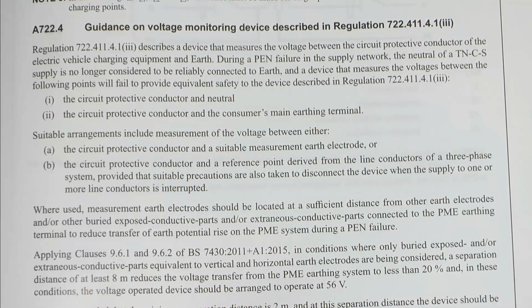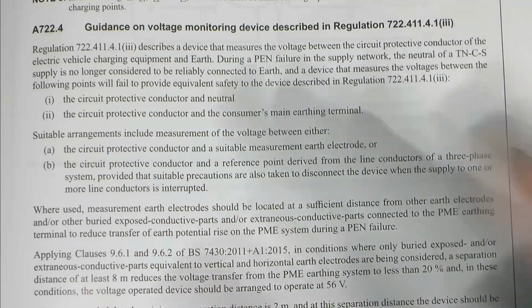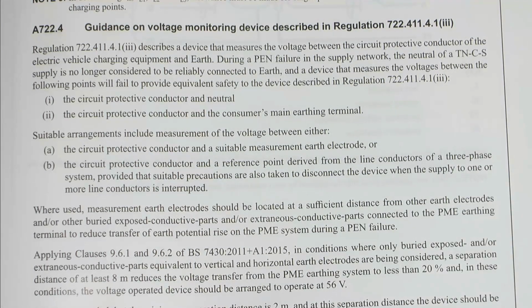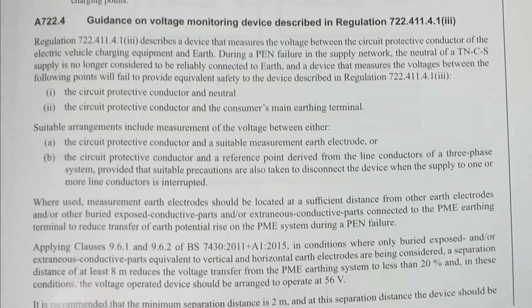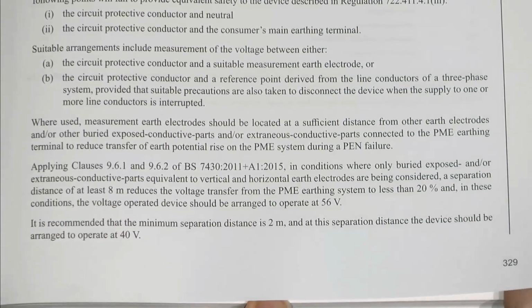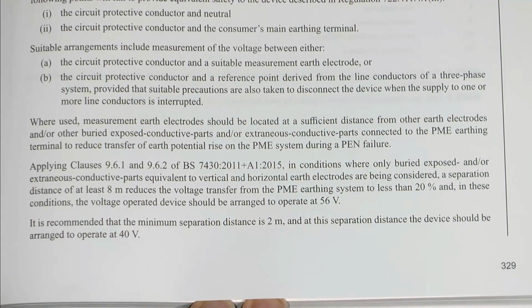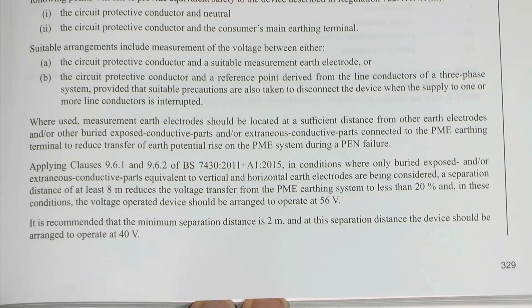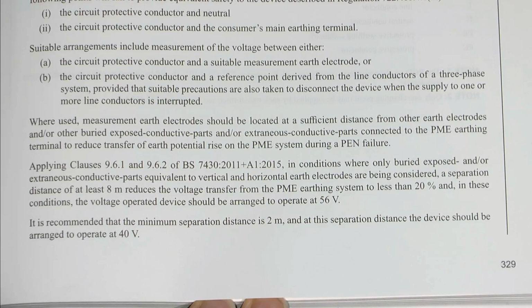Now, where used, measurement earth electrodes should be located at a sufficient distance from other earth electrodes and buried exposed conductive parts and extraneous conductive parts connected to the PME earthing terminal. Because again, if you're going to put a reference measurement electrode in the ground, it's no good situating next to your water pipe that's metal, because that's going to go up to the same voltage in the event of a fault, so that won't work. And there's some further guidance there about the types of electrodes you could use and distances and voltages and so on. So this is a kind of a possibility.